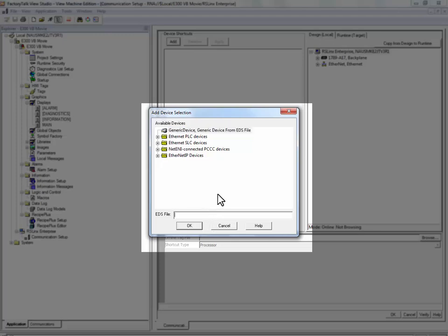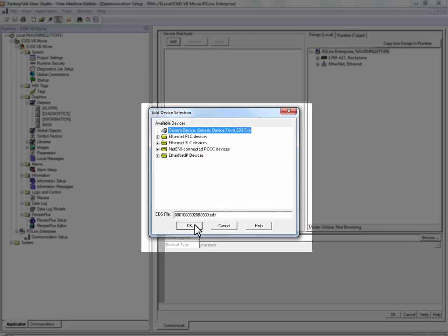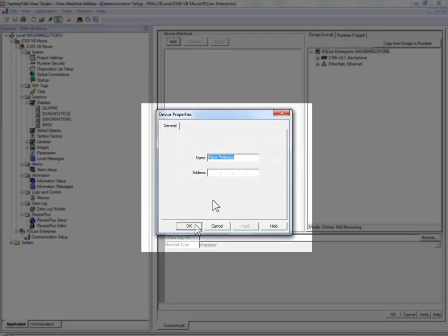Type in the name of the E300's EDS File and press OK. We will name our device Motor Protector and we will be communicating to the E300 located at IP Address 192.168.1.11.